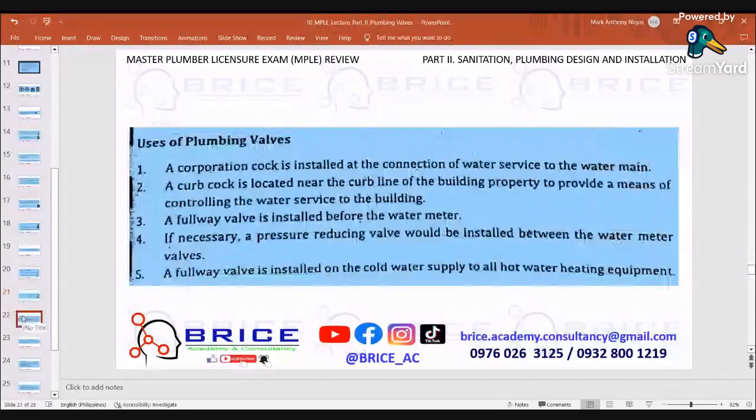Use of plumbing valves. Number 1, a corporation cock is installed at the connection of a water service to the water main. Number 2, a curb stop is located near the curb line of the building property to provide a means of controlling the water service to the building. Number 3, a full-way valve is installed before the water meter. Number 4, if necessary, a pressure-reducing valve would be installed before the water heater. Number 5, a full-way valve is installed on the cold water supply to all hot water heating equipment.